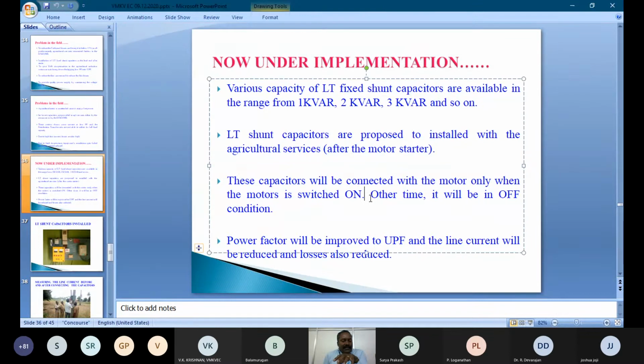The shunt capacitor should not be in service all the time. Whenever the load is available, the capacitor should come into picture. If the motor is switched off, the capacitor also has to be switched off, because if the motor is switched off and the capacitor remains in service, instead of lagging low PF, it will lead to leading low PF, which again creates a problem for the utility. So it is not required.